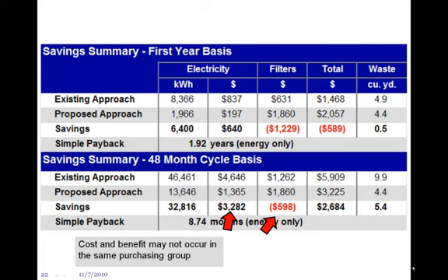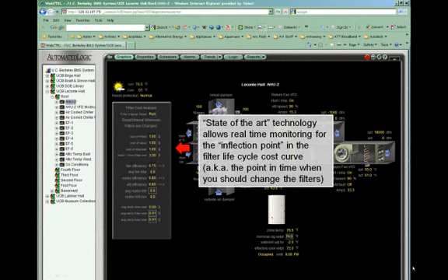It's more than just integrating the systems, which is kind of the commissioning thing. What's really cool about current technology — from that same Berkeley job — we realized that if we had a little table in the control system where the operators could enter what they spent on filters and what it cost to install them, and then tracked filter pressure drop and flow, we could actually draw that filter operating cost curve in real time. We're just getting this running and troubleshooting it — Gary was looking at it a couple weeks ago and found a few bugs, like calibration of the flow sensors. But basically, when we get this working, it'll draw the average daily filter operating cost curve, and this will be what they use to change the filters. They'll watch for that inflection point — when they see the curve bottom out and start back up, they'll order a new filter set, because that's their best life cycle cost. That's leveraging technology to support what we're doing.